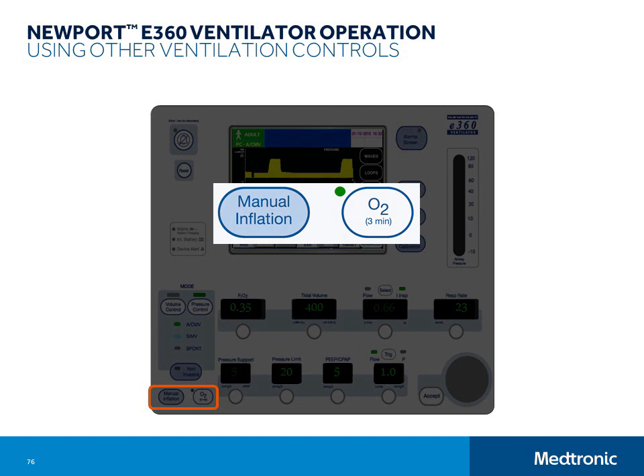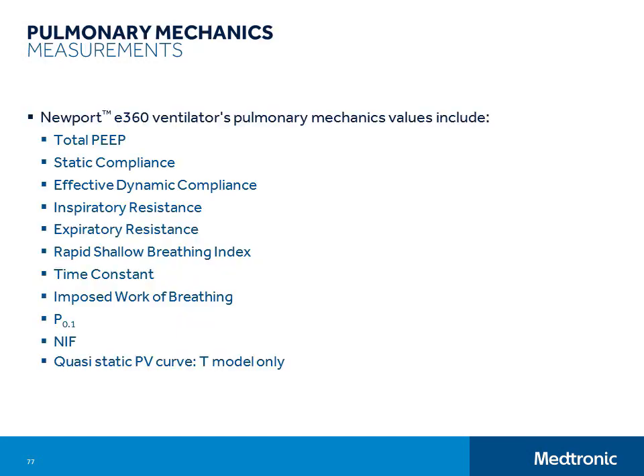The e360 ventilator provides you with a full spectrum of pulmonary mechanics measurements. The values include total PEEP, static compliance, effective dynamic compliance, inspiratory resistance, expiratory resistance, rapid shallow breathing index, time constant, and imposed work of breathing. On the T model, you can also obtain a quasi-static pressure volume curve for assessing recruitability and the lower inflection point. You can view all but the quasi-static pressure volume curve information on the numeric screen. Also on the data subsets that are displayed along the lower margin of the GUI. Touch the Data Set button to scroll through the 4 sets.